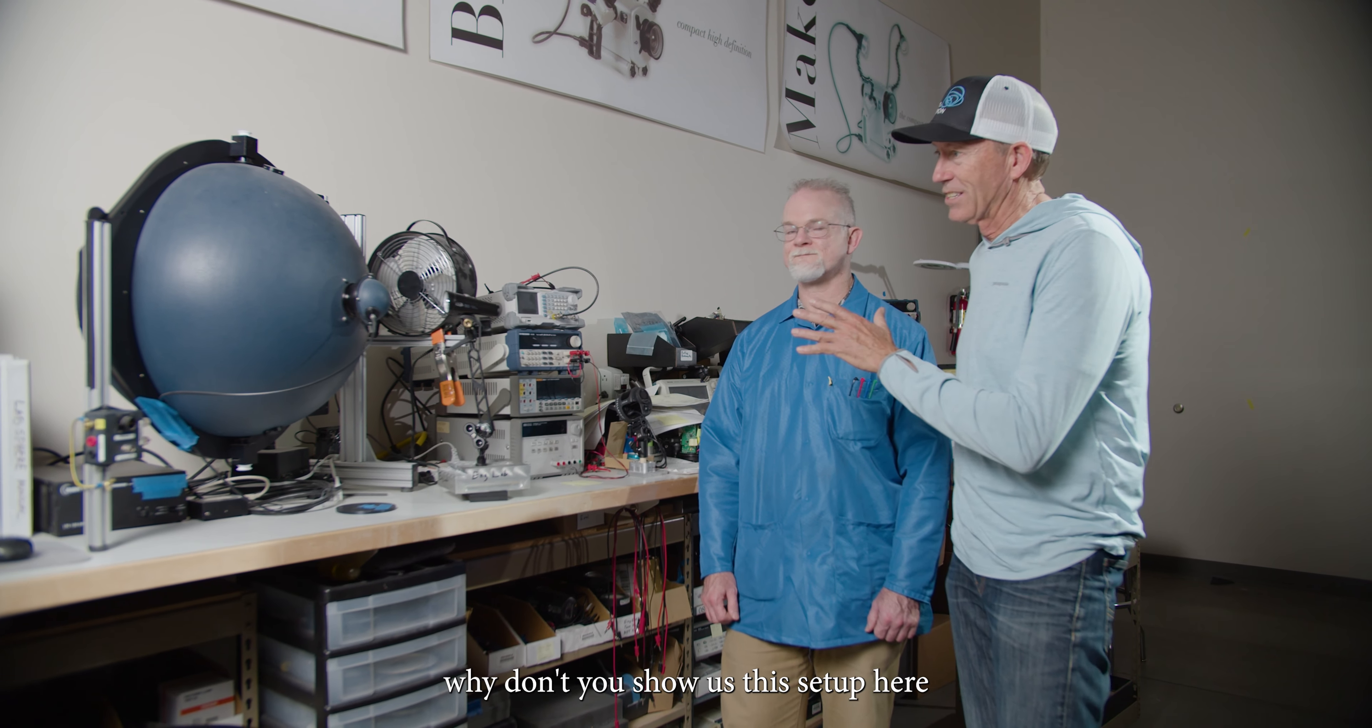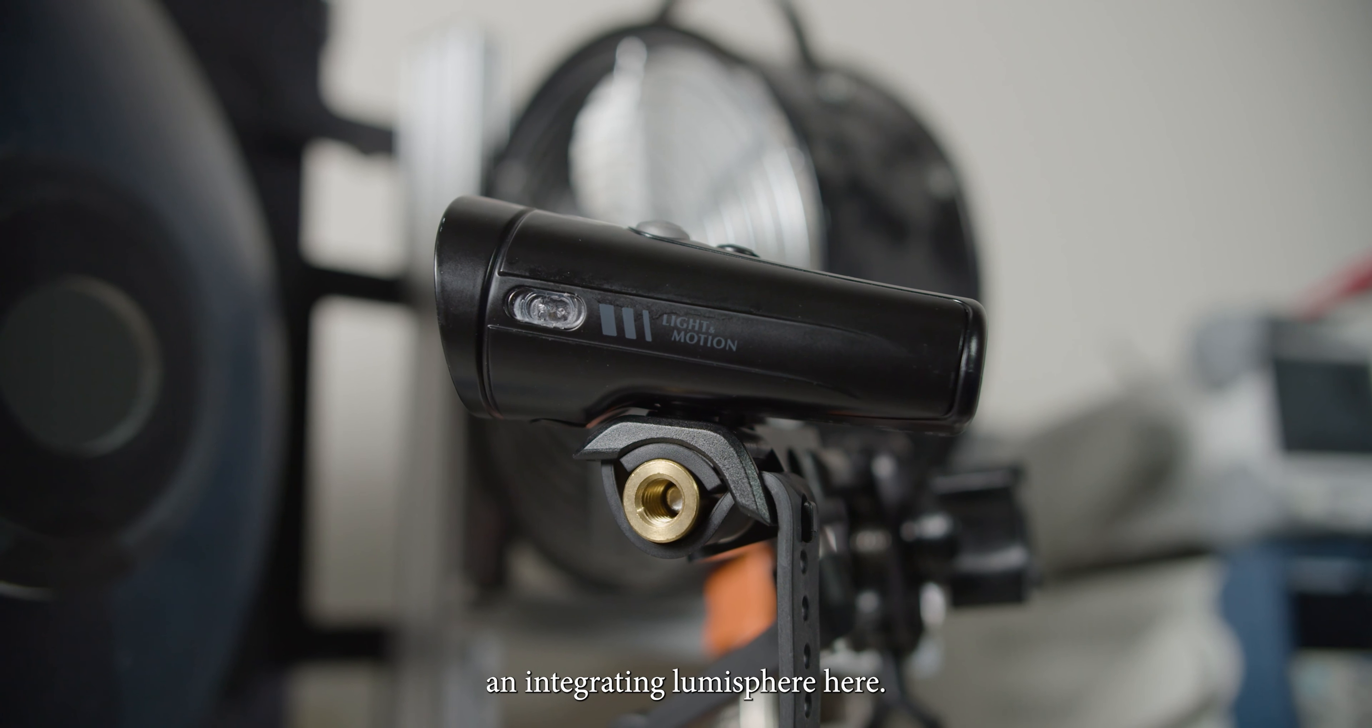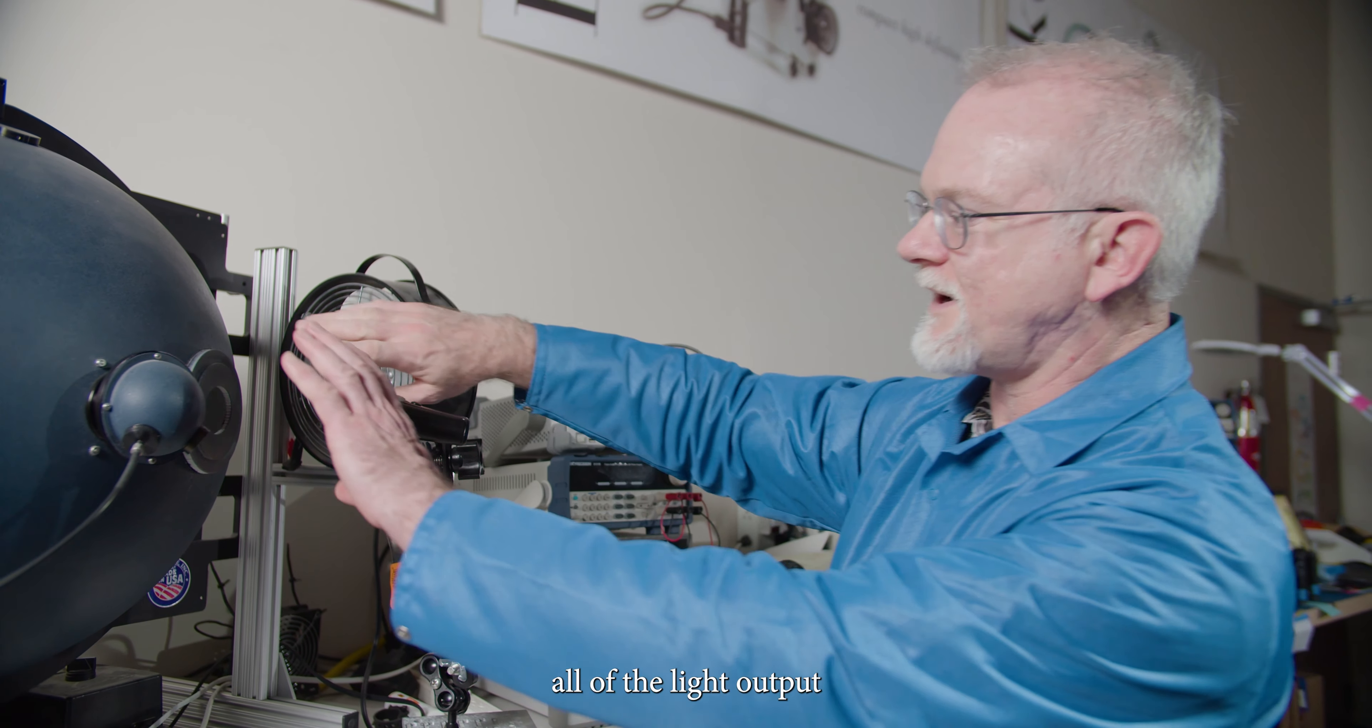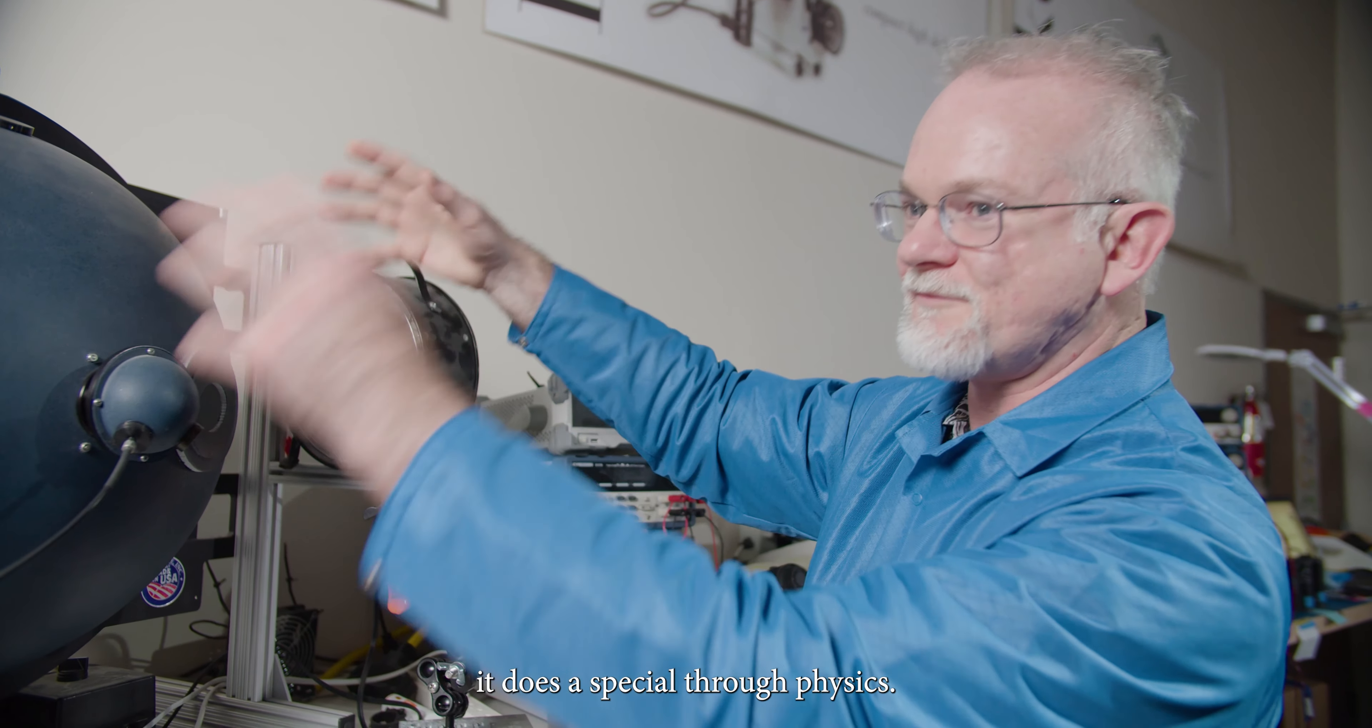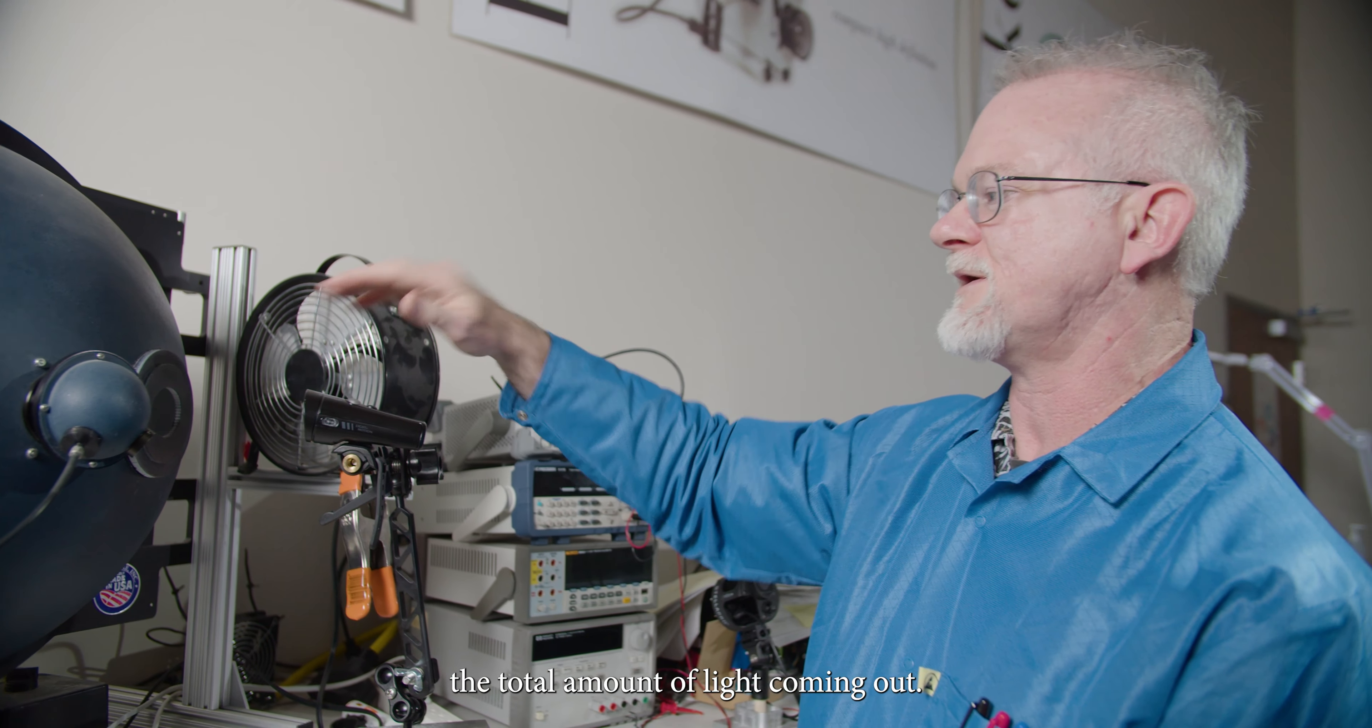Well, Brooks, why don't you show us this setup here and tell us what it does. We've got an integrating lumensphere here, and what this does is this collects all of the light output coming from our unit under test. And it does a special, through physics, it integrates all of that light and then measures the total amount of light coming out.